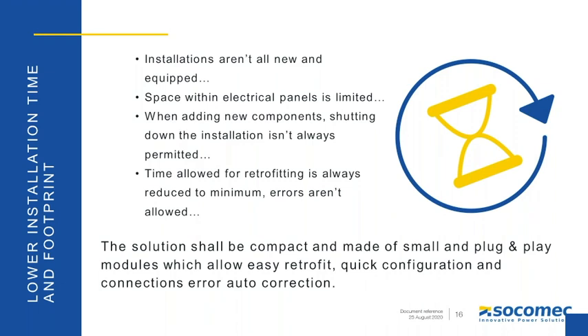The fourth key factor is installation time. Power monitoring is a new trend, and most industries have basic flush mounted meters on the main incoming board, or they don't have any meters at all. So installing a new basic power meter system will become a challenge, as it's going to require significant modifications to the existing installation. Finding space, making new cutouts, having to do the wiring. So it's important to find a solution that can fit in all applications. Power monitoring solutions that are designed for existing panels is a plus. It helps to update the installation with power monitoring without having an impact on the installation, no downtime. Having a solution that minimizes the wiring and the space is optimal for all applications.